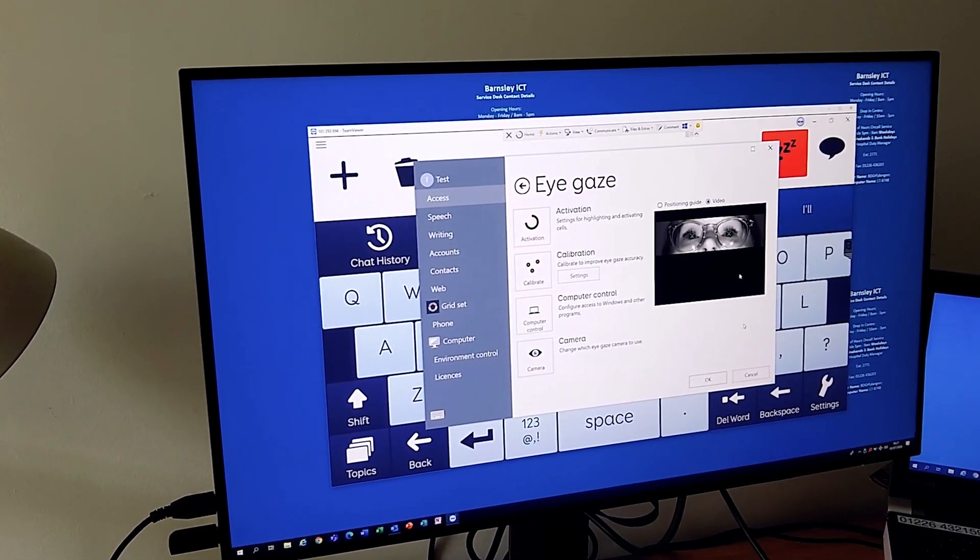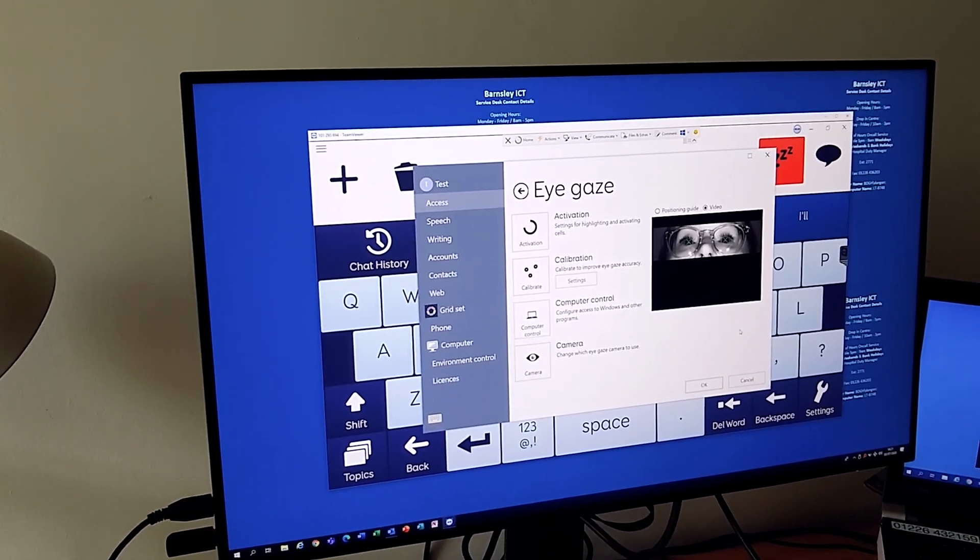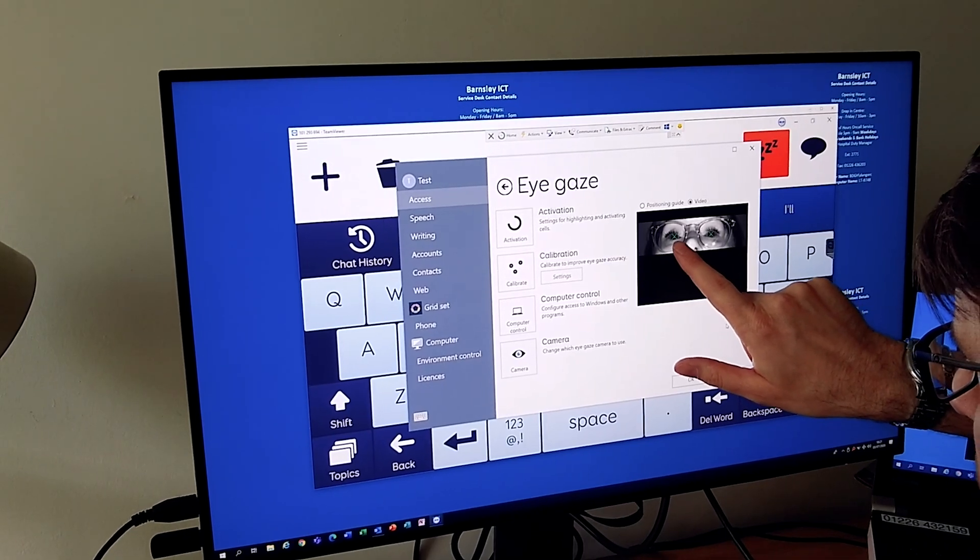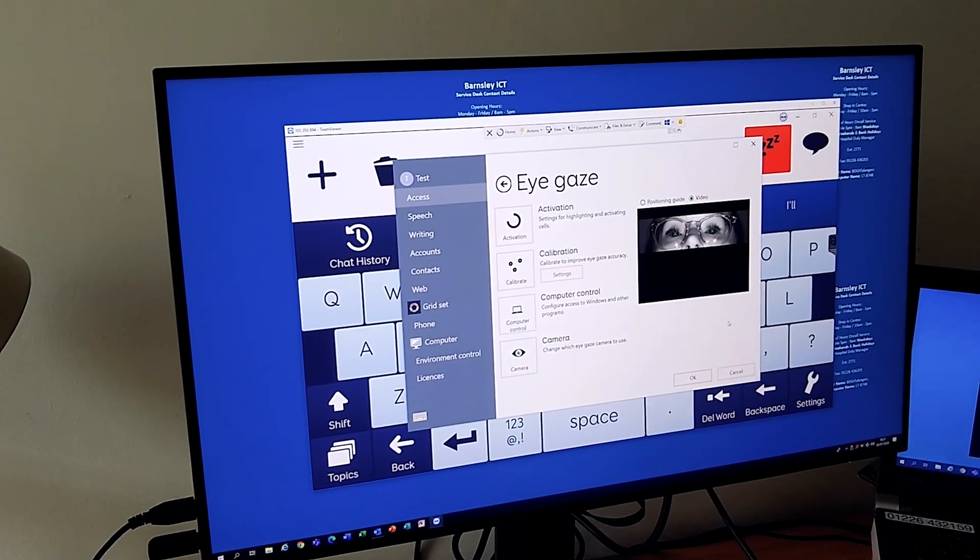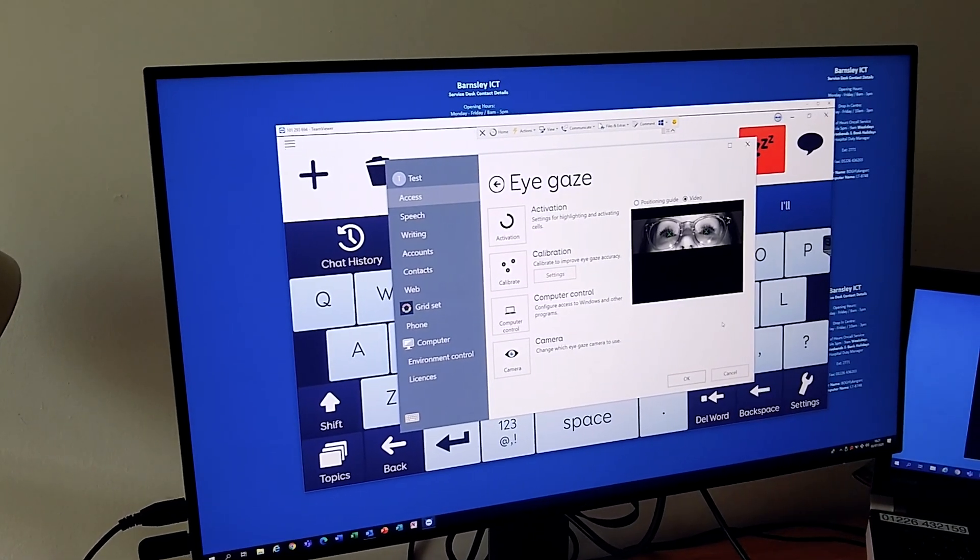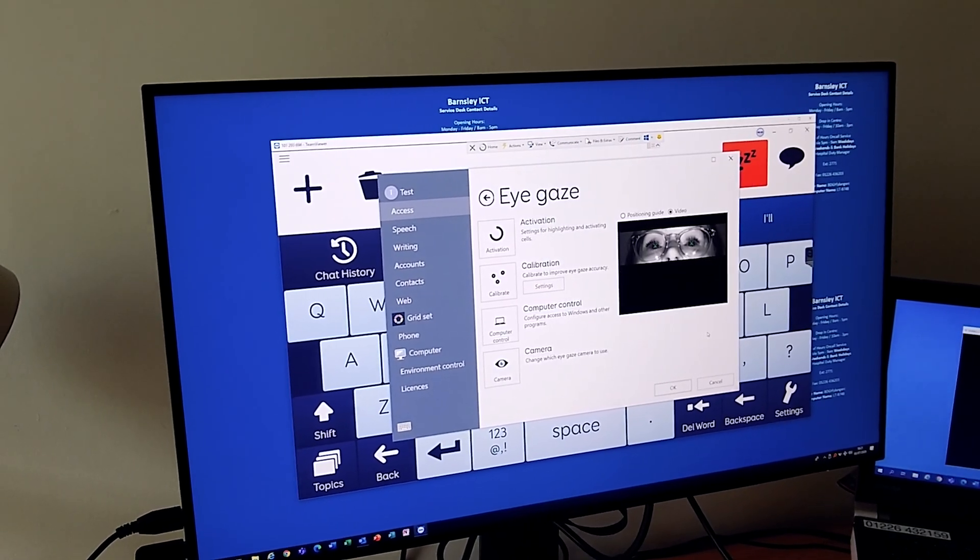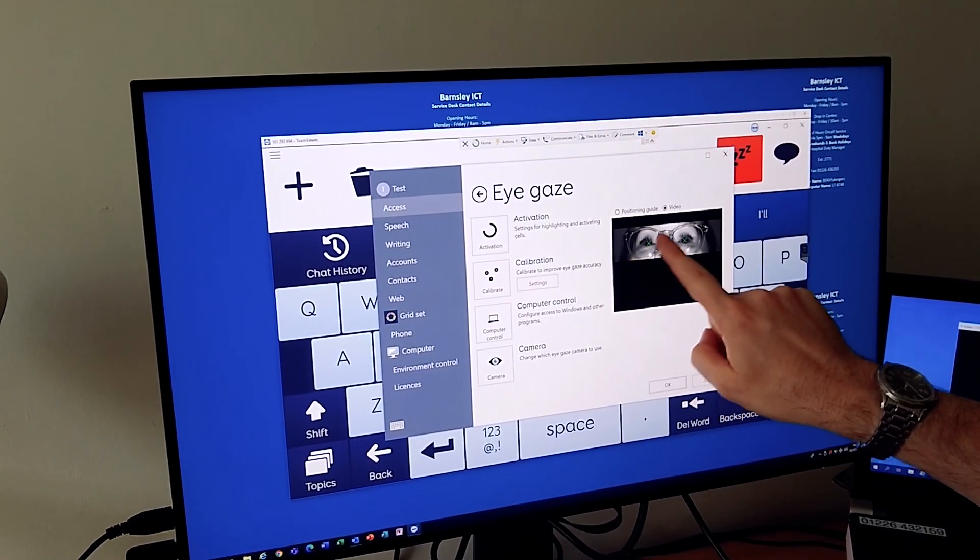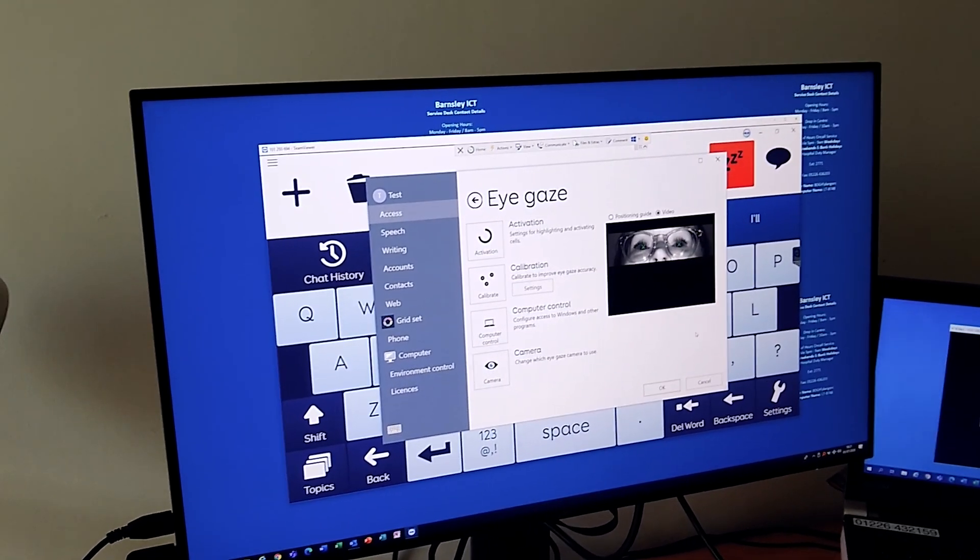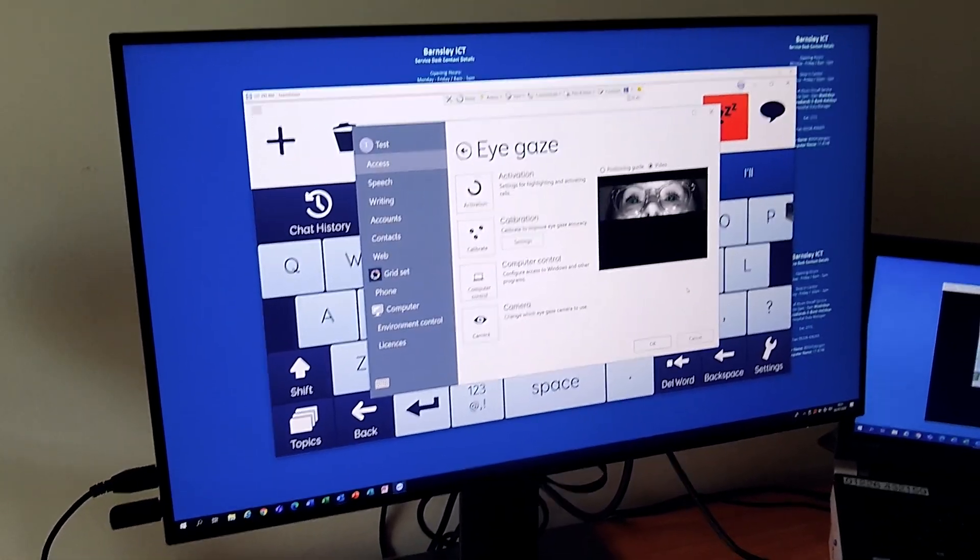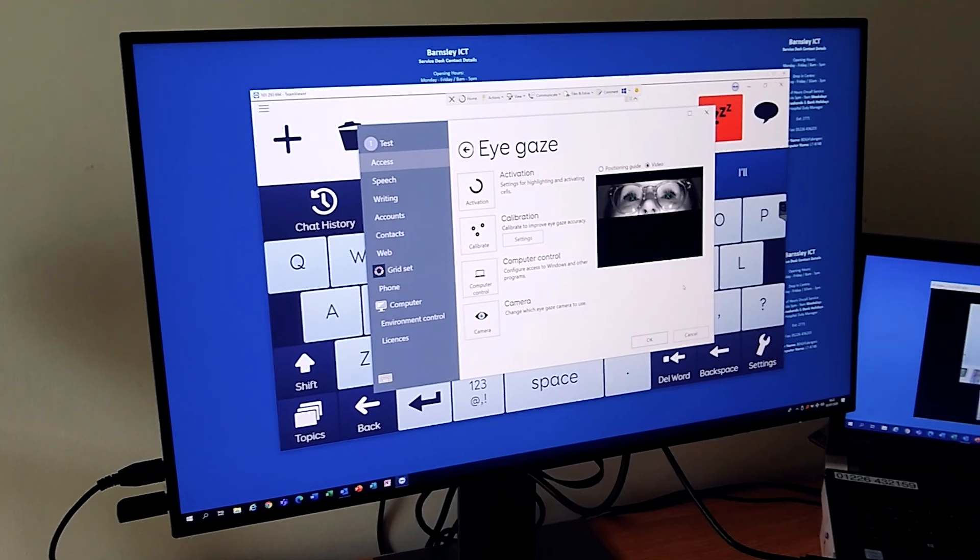On here these green crosses represent the fact that the eye gaze has found the center of your pupil, which I'm very pleased with on both sides. This little white dot near the cross is the reflection from your cornea, so that's the infrared light bouncing back. Those are the things that we really need for eye gaze to work. Your glasses actually have a lot of reflections on them around the frames which may cause an issue—the camera may get confused by that. If that happens we might ask you to take the glasses off or try different type of glasses with different frames.